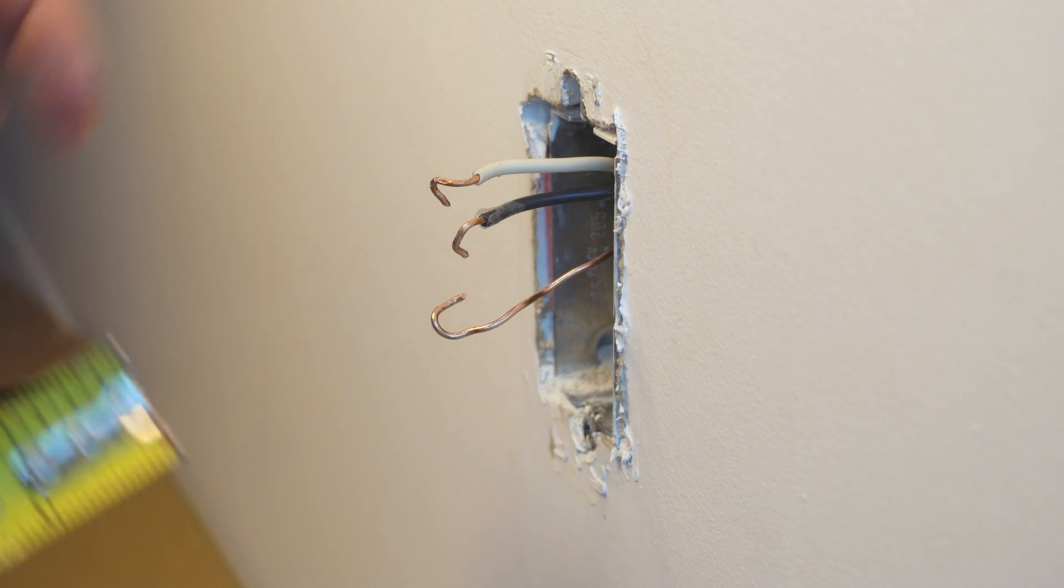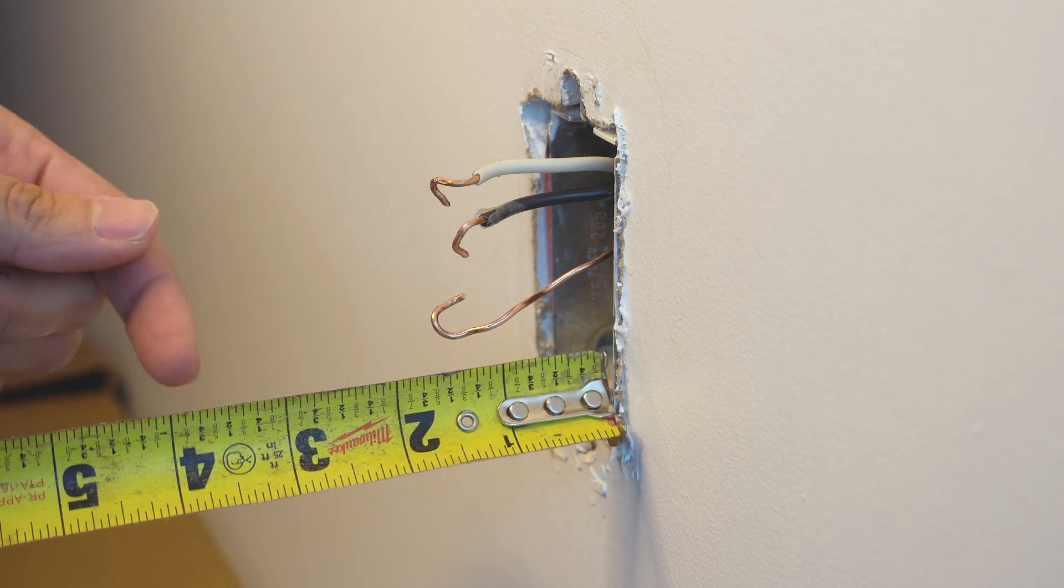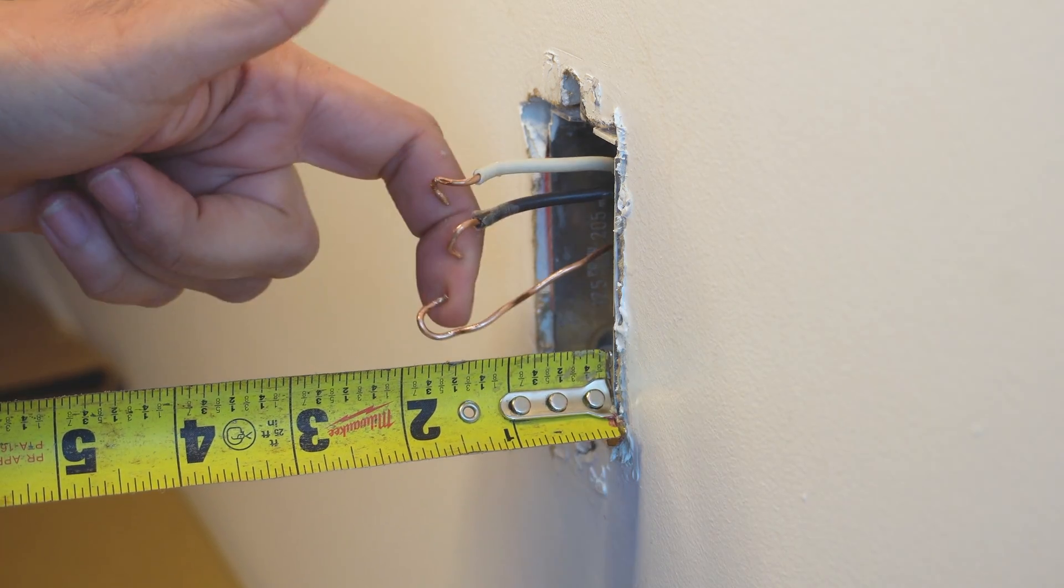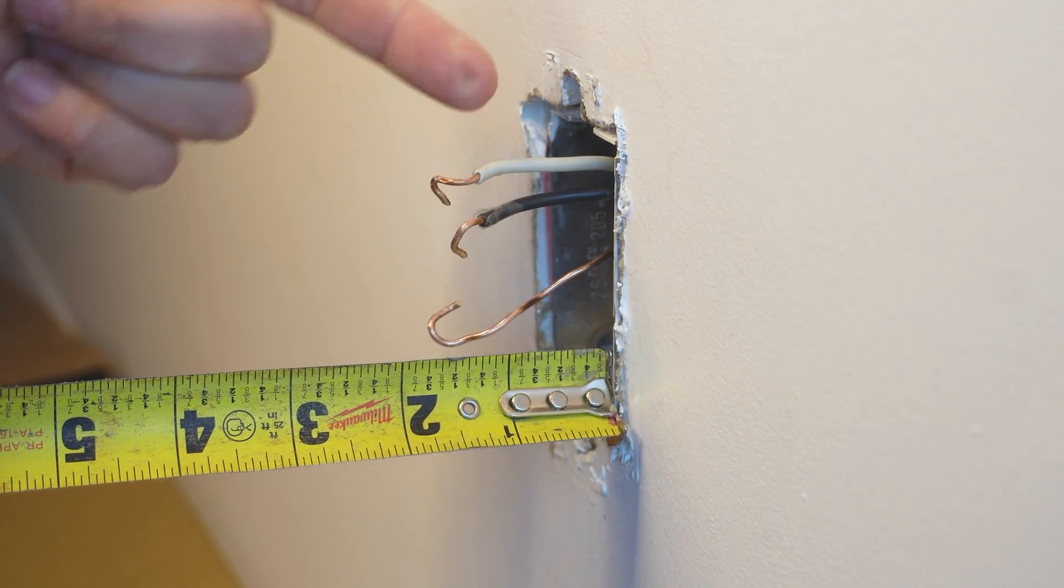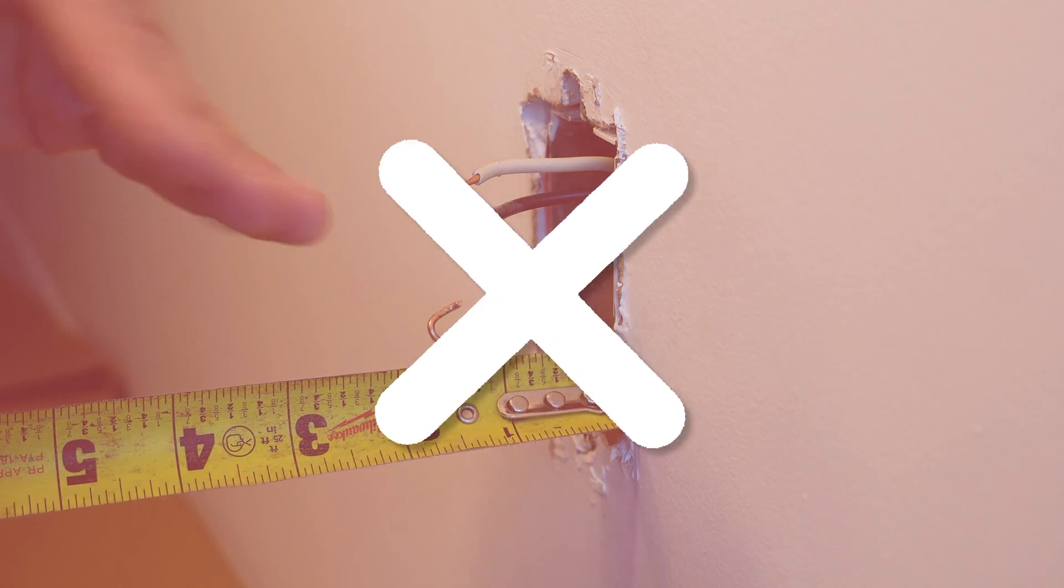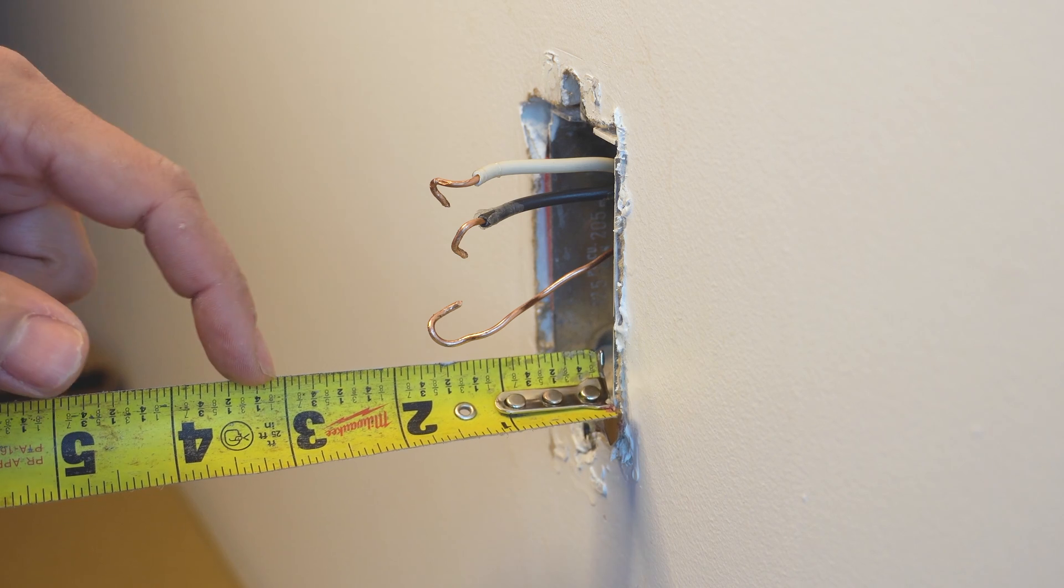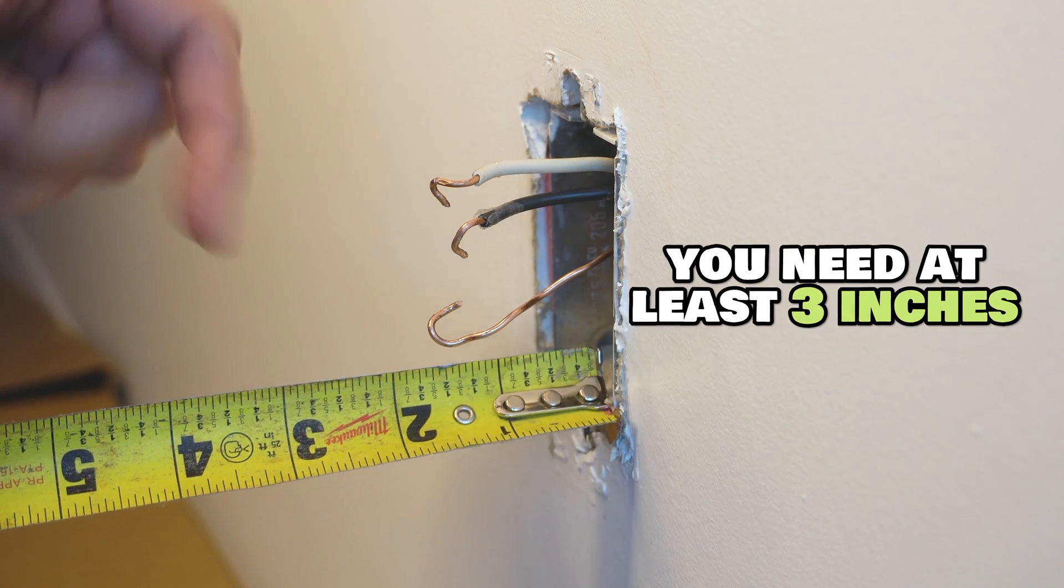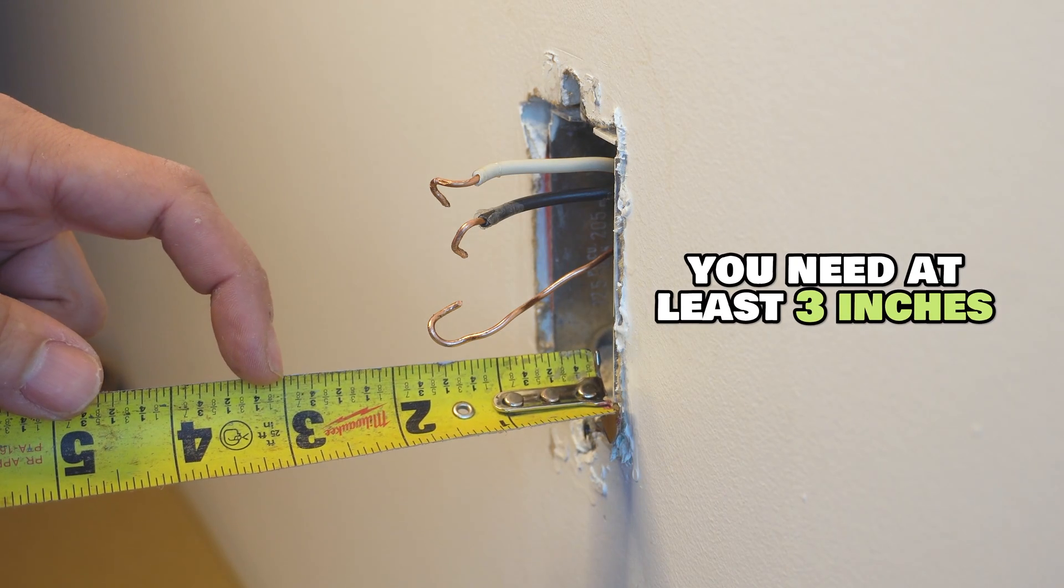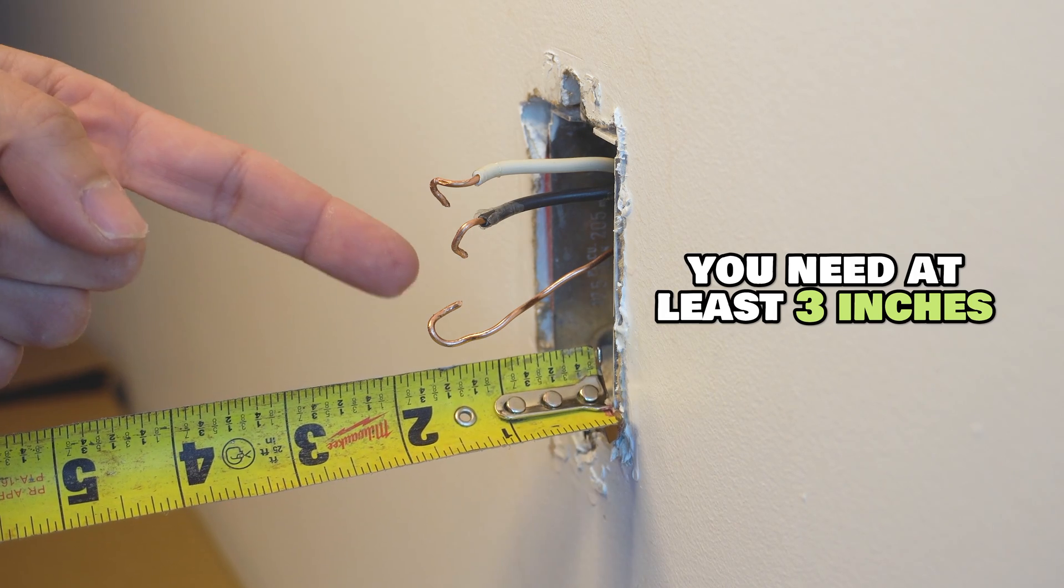Let's measure our wires now and see what we're dealing with. So from the drywall, the projection, it's sticking out only about two inches. This is bad. It's way too short. By code, these wires need to extend from the box and the drywall here, at least three inches away from the drywall. We need to fix this right now.